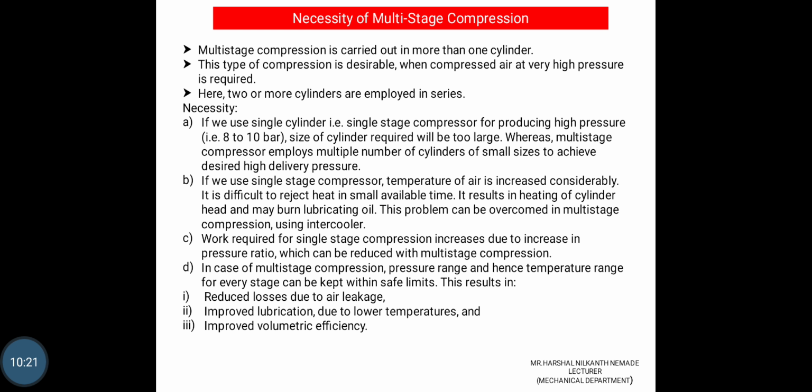Okay, if we use a single stage air compressor, the temperature of air is increased considerably and it is difficult to reject the heat in the small available time. It results in heating of the cylinder and may burn the lubricating oil. This problem can be overcome in a multi-stage compression using an intercooler.